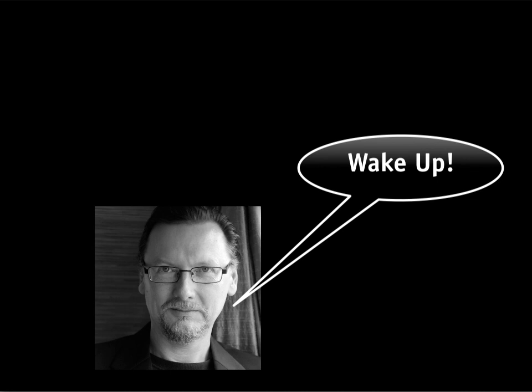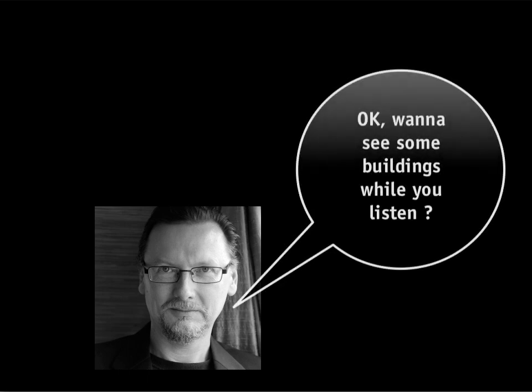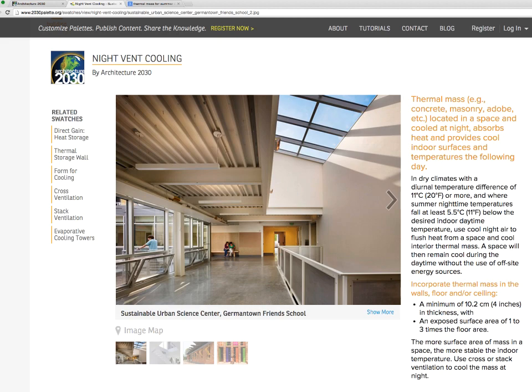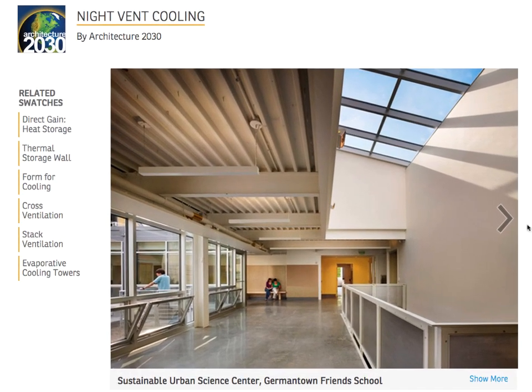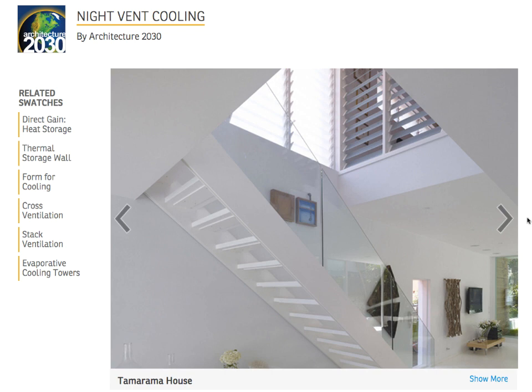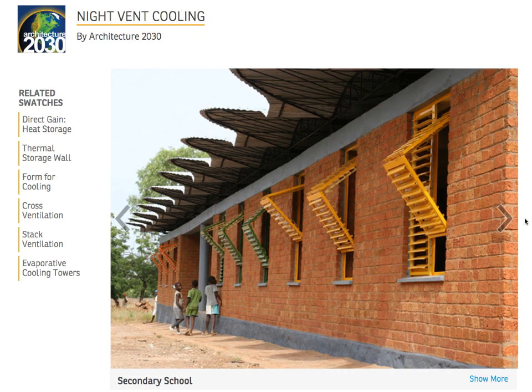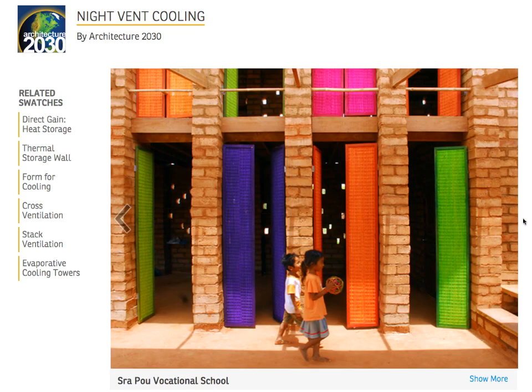So in many climates, what that means is that beyond about 80, 85 degrees, depending on what your tolerance is, you want to close the building. So there's a lot of time above 80 degrees, let's say in Knoxville, Tennessee, or Phoenix, Arizona. So there are plenty of months, or at least days or weeks or times of the day, when open natural ventilation is not going to be a benefit. It's too hot to ventilate, we say. So the solution for that, or one of the solutions for that, is night cooled mass. Night cooled mass is a kind of hybrid strategy of being open and being closed. When it's too hot to ventilate, we close the building. So sometime in the morning in the summer, it gets up above 80 degrees, and we have the building closed.